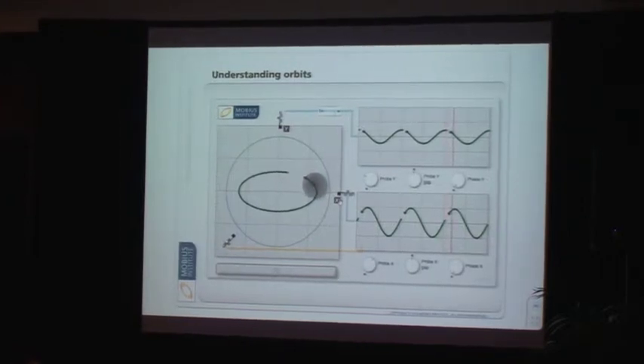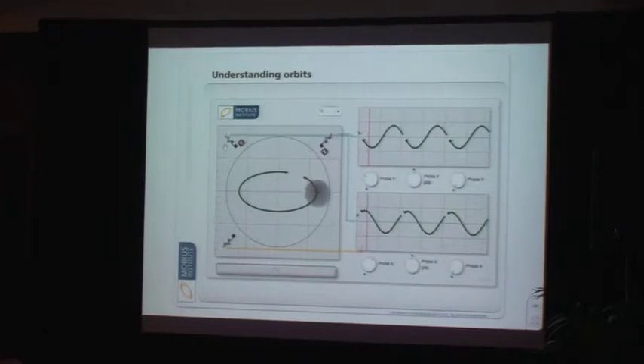What are the probes actually seeing? Are they seeing that full motion, or are they just seeing it from their perspective? So depending on how that orbit changes because of the forces on the machine, what are we actually going to see? And that's why there's a parameter called S max, which from the two signals says, well, your maximum displacement is what we are actually looking at right now. But in any case, we start with these two signals, and we can create the orbit from that.